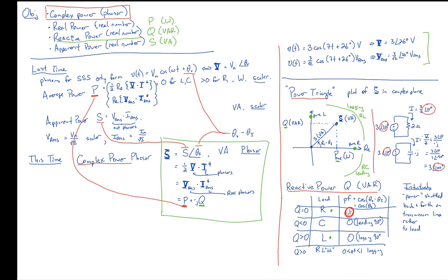If there's an industry that has a power factor of its load that looks like 0.85, I promise you they're getting slapped with a heavy fine from the power company, because the power company wants to somehow recoup its losses from all that reactive power that's being sloshed back and forth from the transmission lines, but isn't showing up on that company's power watt meter as being actually used. So reactive power is that portion of the power that's sloshed back and forth that's not used.